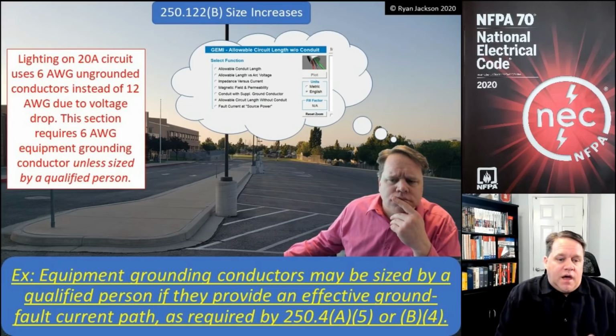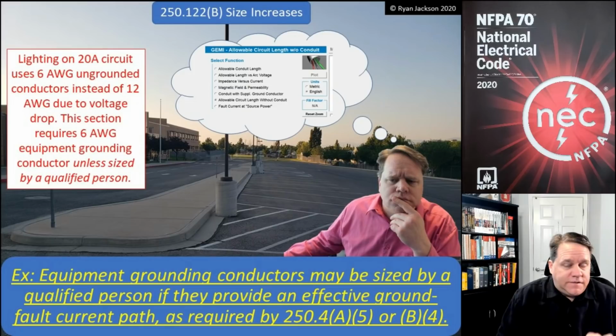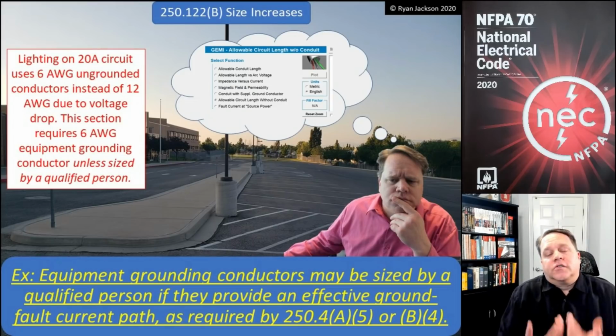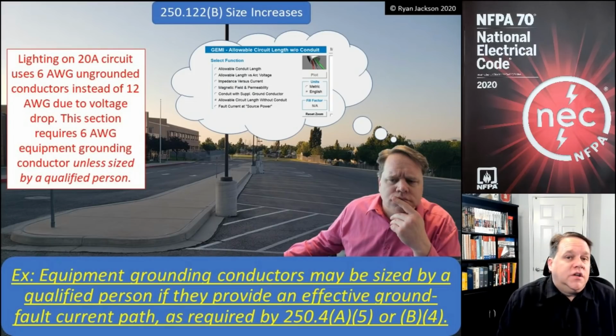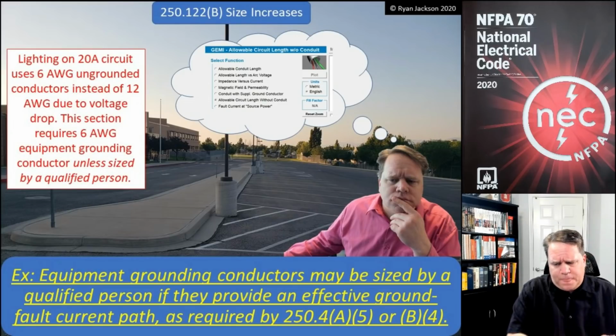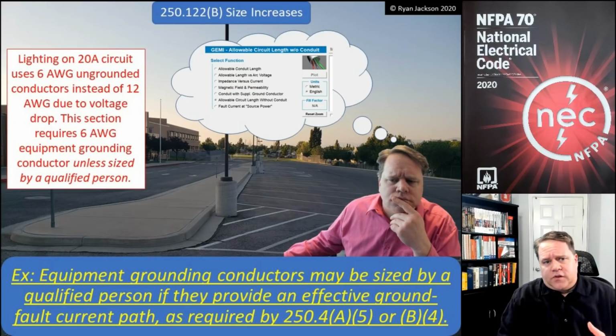So this is saying, as long as a qualified person can size it and ensure that it's going to have an effective ground fault current path, then let's let the qualified person do it. It doesn't even need to be an engineer. Now, that's a little bit surprising, because when it comes to sizing equipment grounding conductors outside of what the code gives us, you might think that we would have to start looking at damage curves and different things and figuring out impedances and all of that, and maybe that should require an engineer.